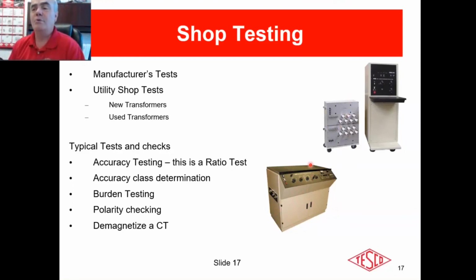So why would you use these? Well, you would use it on your new transformers to do a check of your new transformers. You can either do a selective test or a statistical test of a new batch of transformers, or our recommendation is a full test. Why do we recommend a test of all of them? Because we suggest that you test all of your instrument transformers and all of your transformer rated meters in the shop before putting them out into the field. Why?